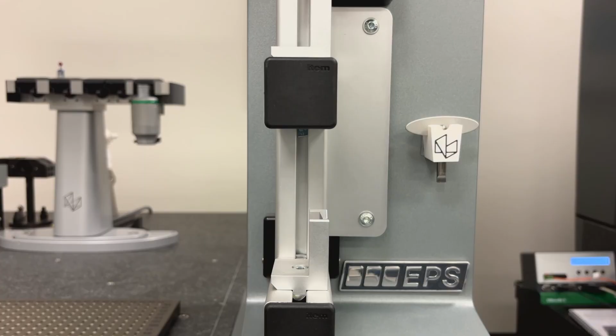So I've taken that first hit, and then it prompts me to take a hit on port 4, which is the bottom one. And now here is a close-up of where those hits are being taken at. This first hit is demonstrating a horizontal hit on the vertical surface. And then the next hit is going to demonstrate a vertical hit on the horizontal surface somewhere between the side and the screw. I'm then going to take another vertical hit on the third port. Here it is from the other angle.